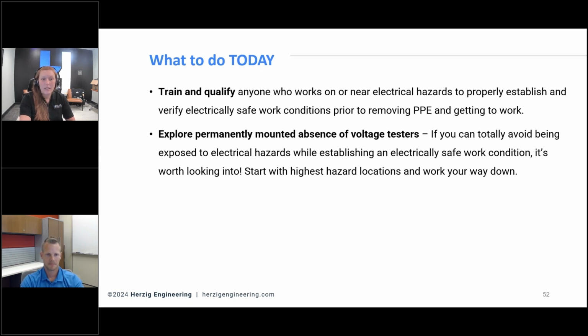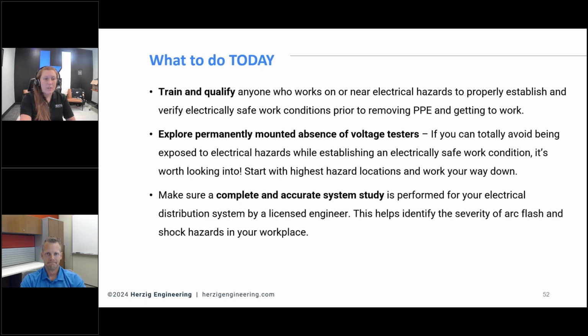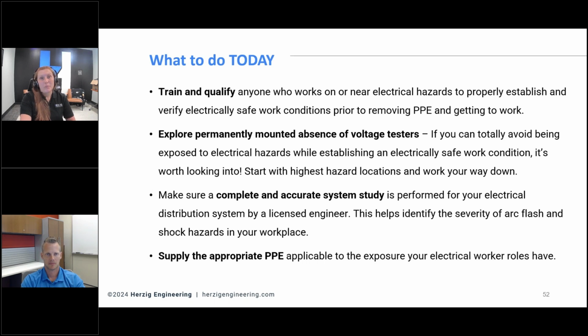So at least give it a think through, look at your equipment, maybe have a priority level list, things that are most frequently accessed and or highest hazards. I would say those are the places to start exploring these options. Do have a complete accurate system study, because that PPE they have to wear, if you don't have the absence of voltage testers especially, that's only going to be able to be determined if you know the severity of the hazards. And then of course supply the right PPE to make sure they're safe as they're verifying.